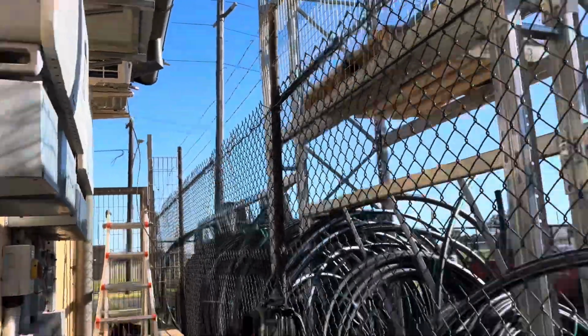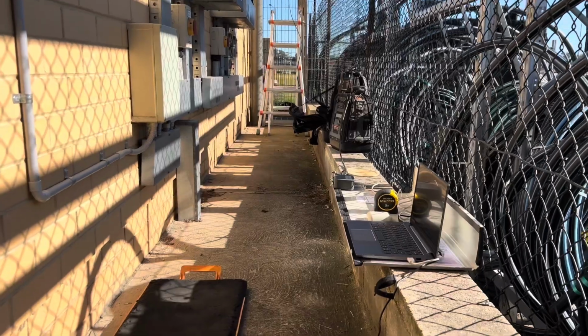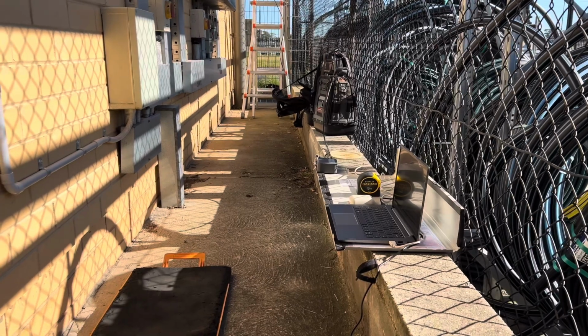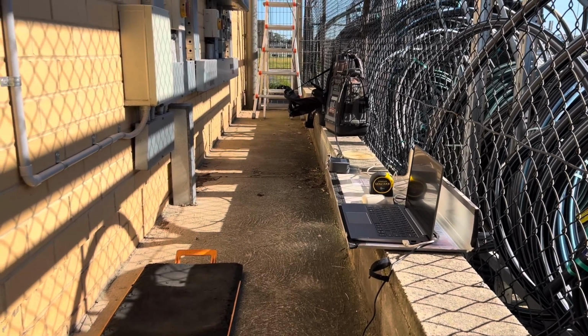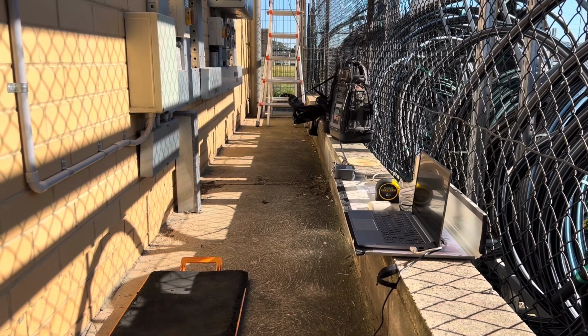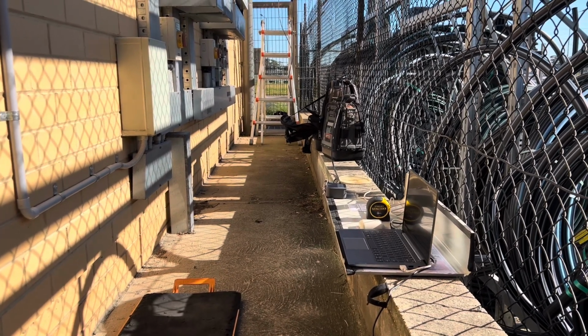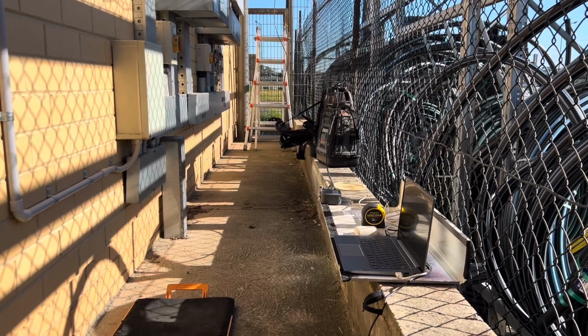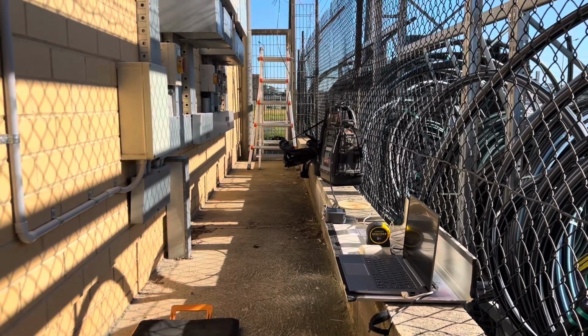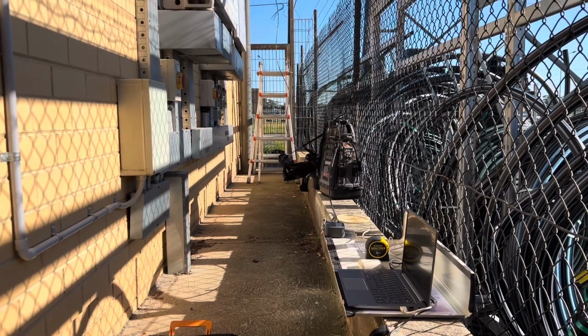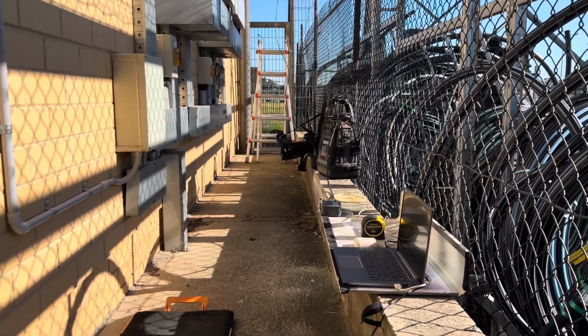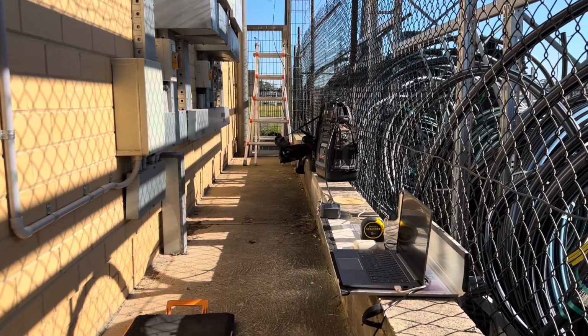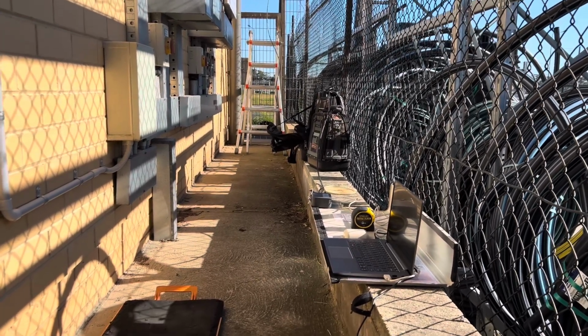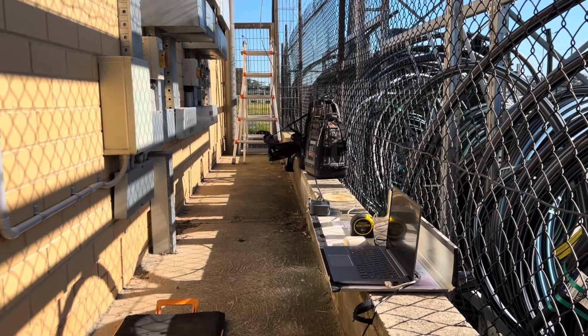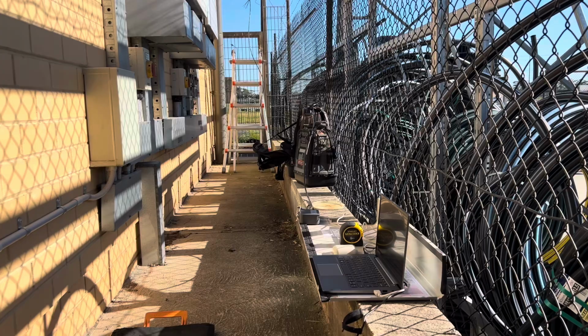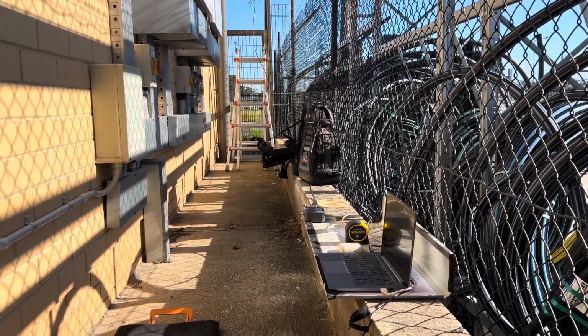System's actually just gone into a defrost, so both units are now running. I've changed the master controller to read from the lunchroom there, so it's obviously a high use area. It's colder, they leave the door open. The office is a smaller space and the doors are closed, and realistically there's one person in there, maybe a quarter of the day. So having the master set to the lunchroom is going to eliminate that office unit banging on, heating up, going into cooling, banging off. I've also spoken to the external company that runs the BMS here, and they've taken all the prohibits off the controllers now.